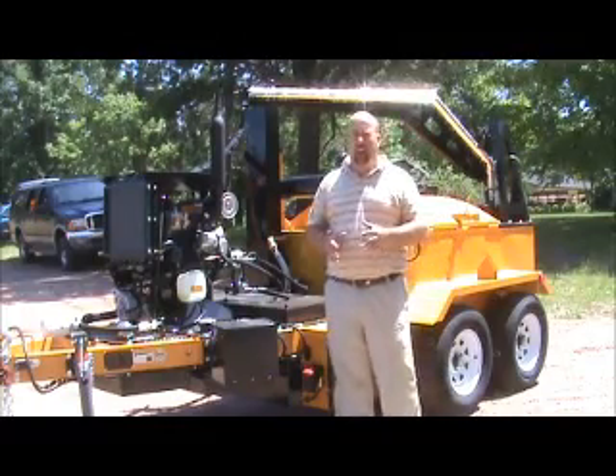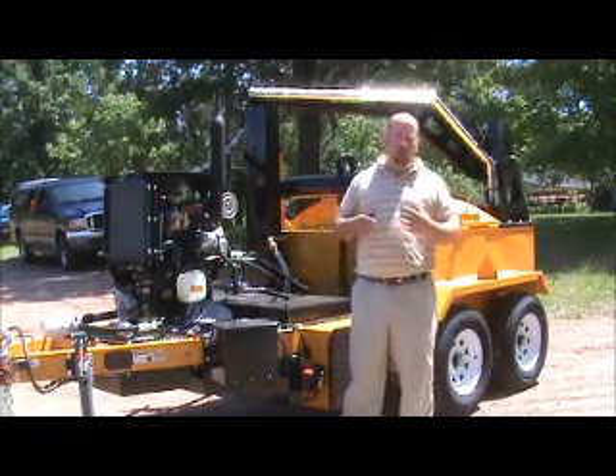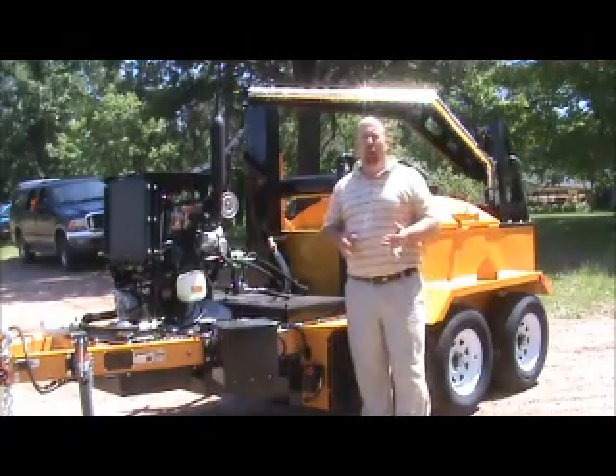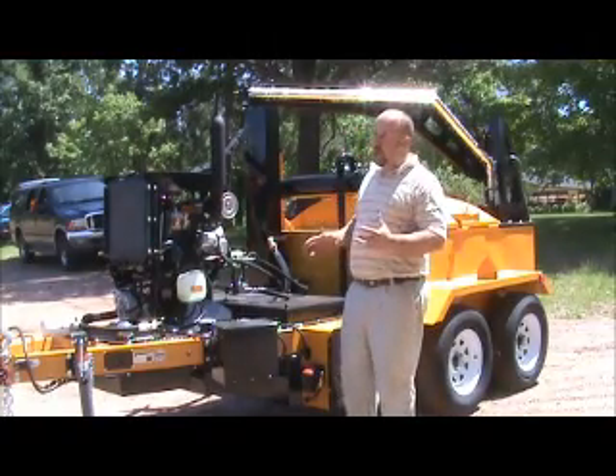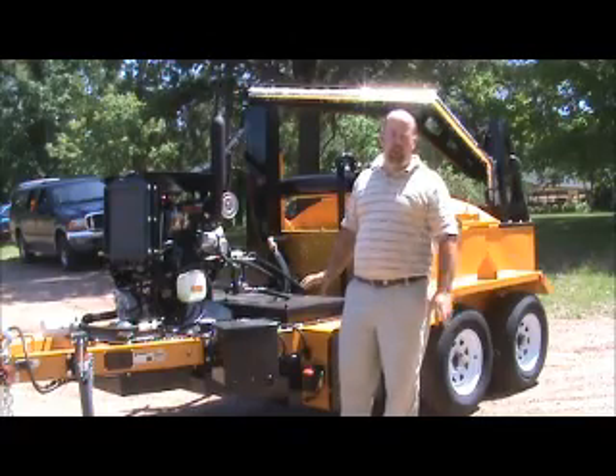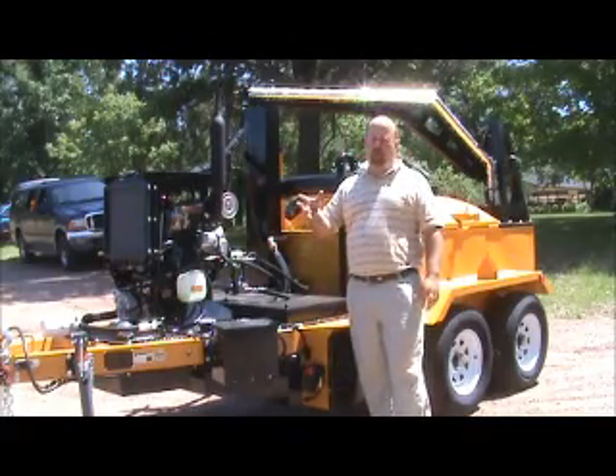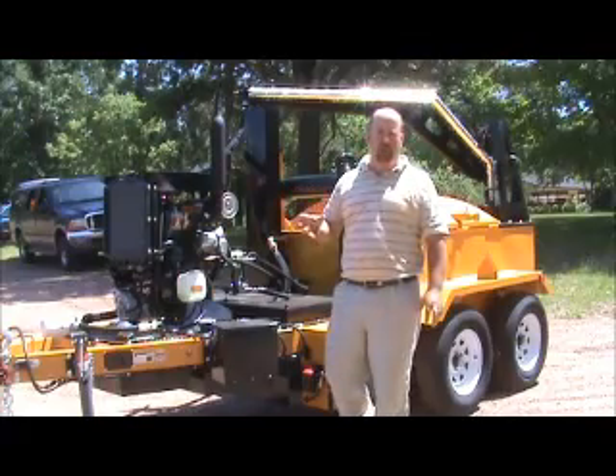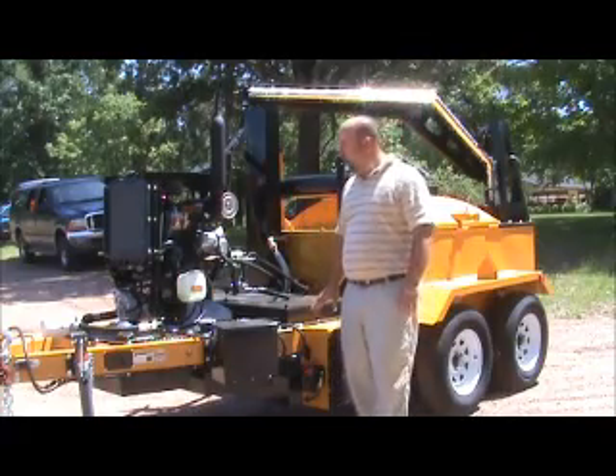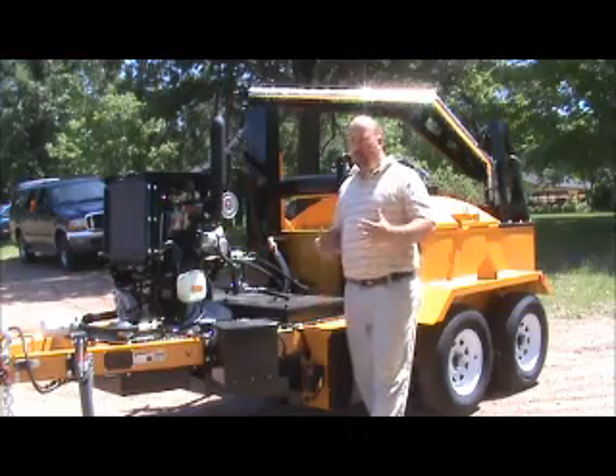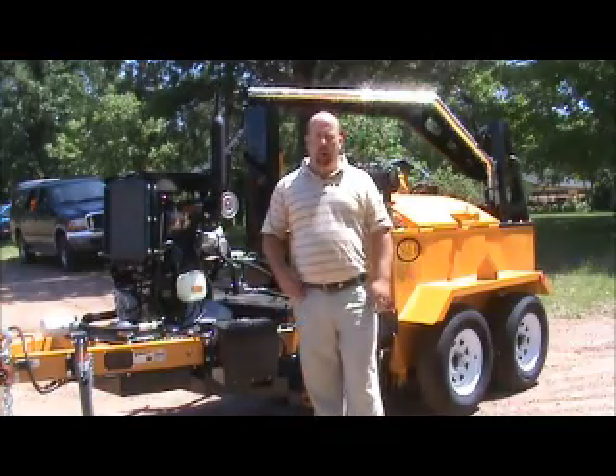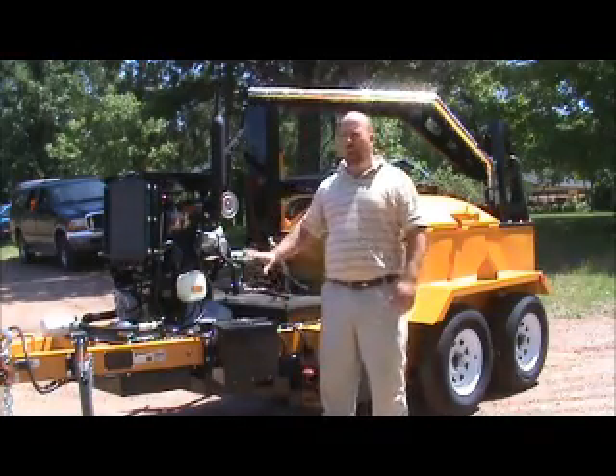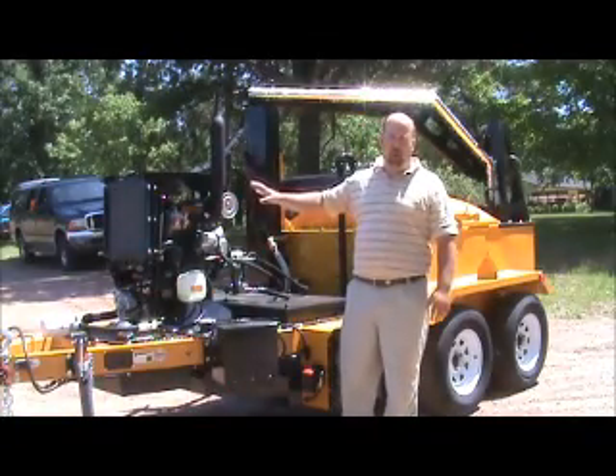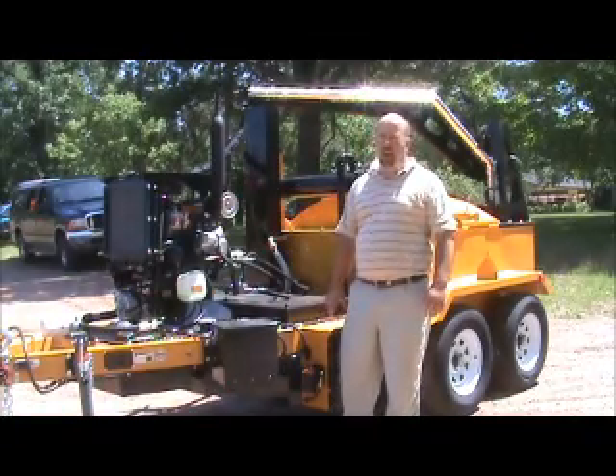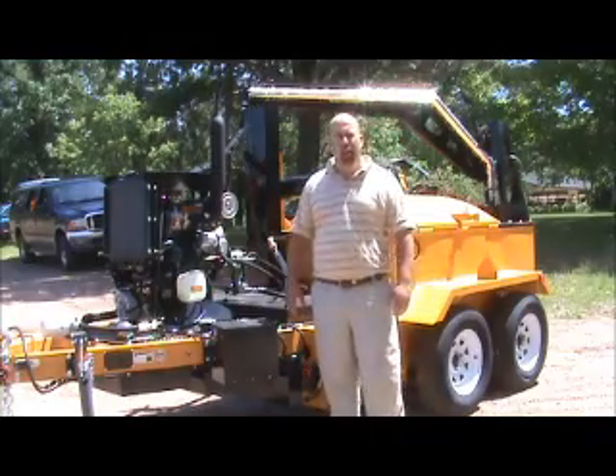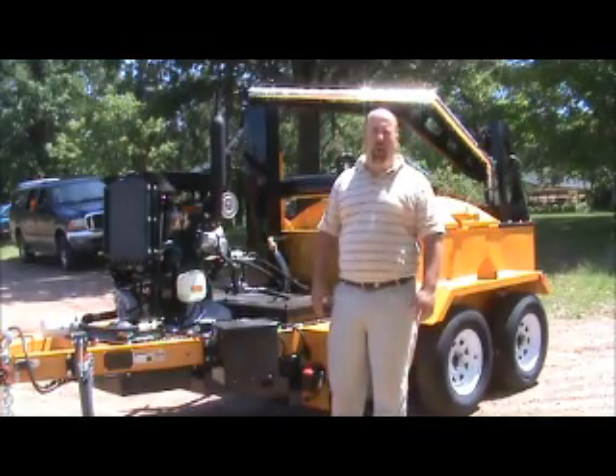The diesel burner doesn't care whether we burn a number 2 fuel, a blended fuel, or a number 1 fuel. If you do change to a number 1 fuel, you're going to have to make some minor modifications, or not modifications, but adjustments to the burner system to burn with the higher quality fuel. The question always comes up with biofuels. Biofuels, anything up to a B5, the engine manufacturer will warranty that, and also the burner manufacturer. When you start to get into fuels that are higher than a B5, you do run into cold weather starting problems.